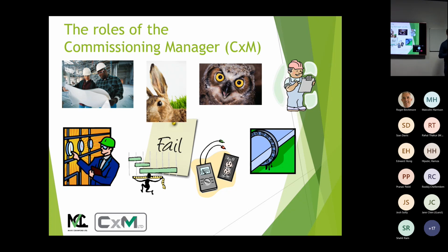Commissioning valves, for instance - if you go onto any site whilst they're being installed, they'll probably be close coupled to the next item because it's easier than cutting a short piece of pipe and fitting the necessary straight lengths of pipe the manufacturer recommends. But on the floor there'll be the box the valve came out of, and if you pick the box up and open the instructions, it shows a diagram of what the straight lengths of pipe should be. So quite often we'll pick them up and show them to the installer, and they'll say 'oh, I've never seen that before' - well, there's boxes everywhere, look, they've all got them in. So these are the sort of things we pick up.